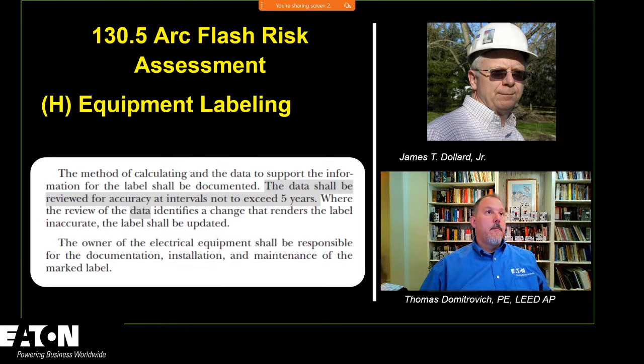The last sentence is one most people don't read. They say, hey, you have to label everything. Label, label, label. 70E says you have to label. Well, the owner of the electrical equipment is responsible for documentation, installation, and maintenance of the marked label. If labeling on the load side of the service point was a requirement in the 1910 General Industry Standard or the 1926 Construction Standard, then 130.5H for equipment labeling in 70E would be a requirement.